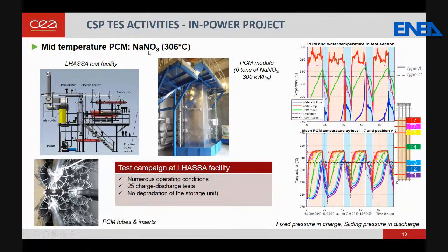In this case, sodium nitrate is a really good candidate. We have already demonstrated in previous projects the thermal performance of such storage systems using sodium nitrate. It's a tube and shell storage system, where water and steam flow within the tubes, and the tubes are immersed in a bulk volume of phase change material. One drawback of sodium nitrate is its low thermal conductivity, which is why we use fins and longitudinal inserts to enhance heat transfer between the steam and the phase change material.